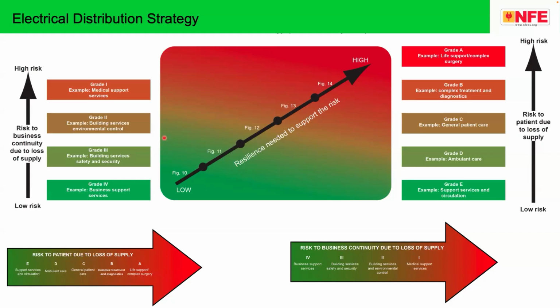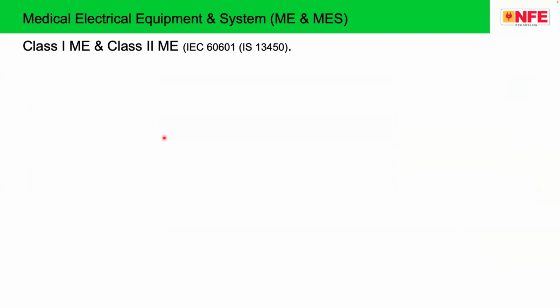In the next slides, I will explain how scientifically this has been developed over the years. In a medical location where a medical activity or clinical process is going on, medical electrical equipment is required. We call them biomedical equipment. The correct technical term is medical electrical equipment. ME stands for medical electrical equipment. MES stands for a combination of medical electrical equipment, which is called a medical electrical system. They are classified into Class 1 and Class 2. Normal electrical equipment which we use in our houses is classified as Class 1, Class 2, and Class 3, whereas for medical electrical equipment there are only two categories, Class 1 and Class 2.